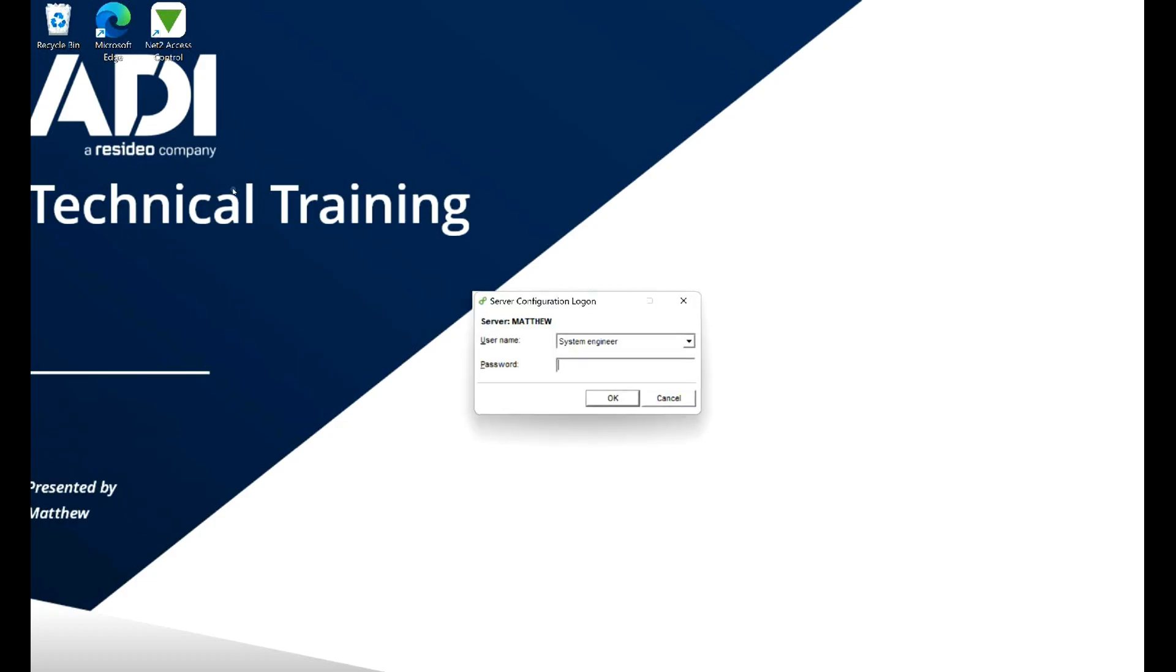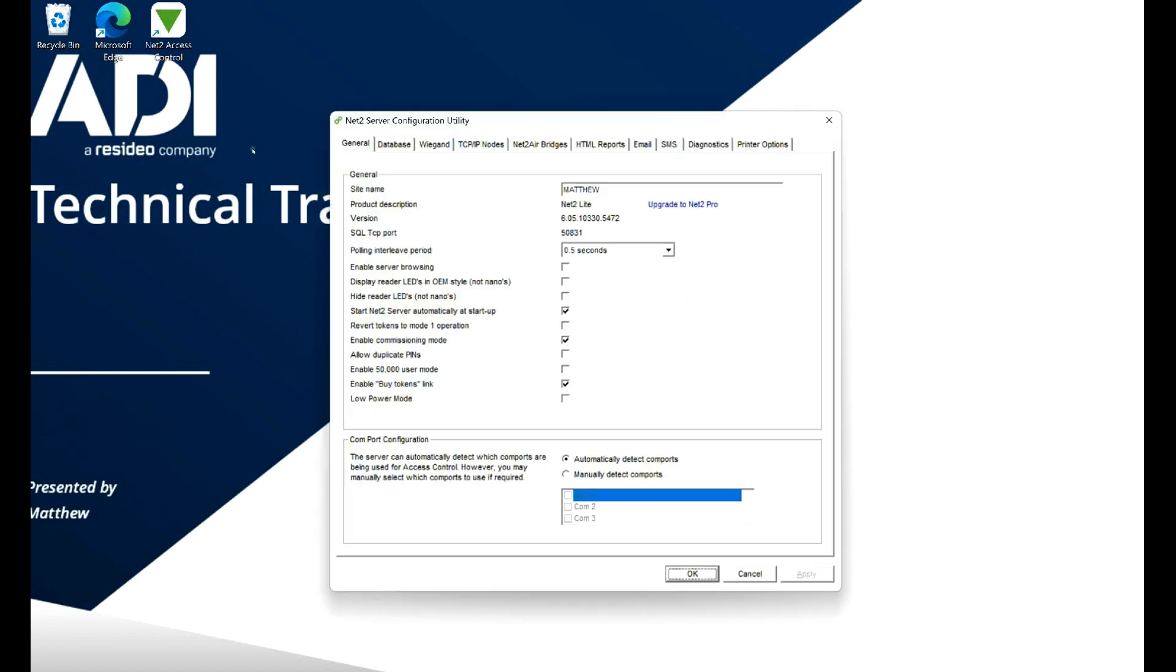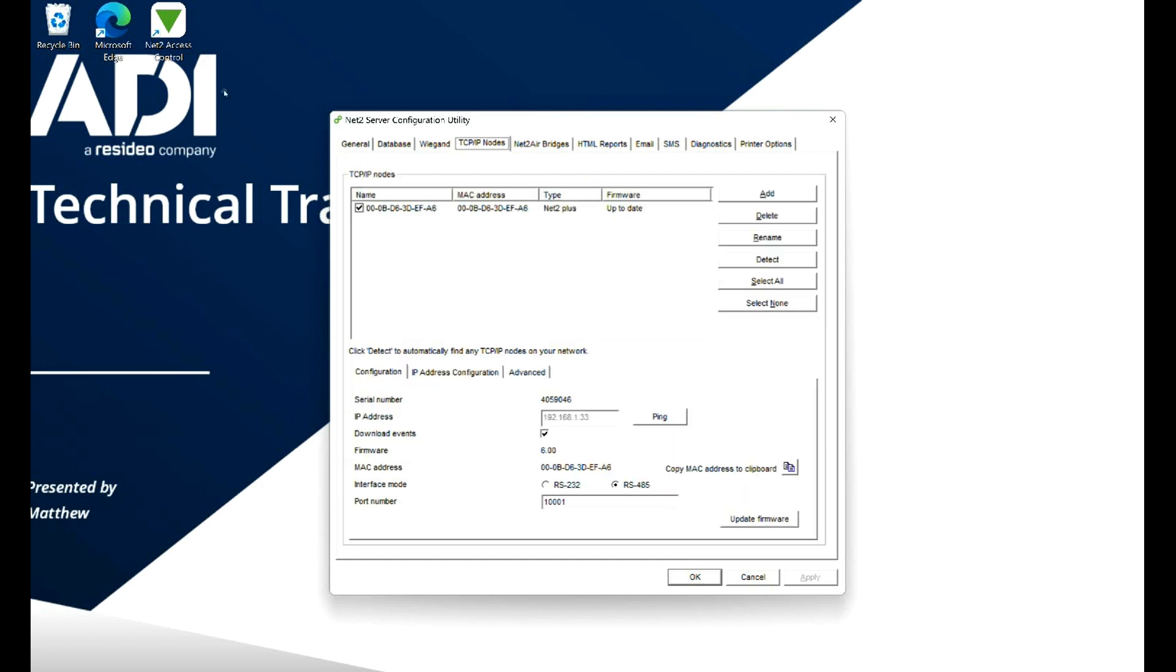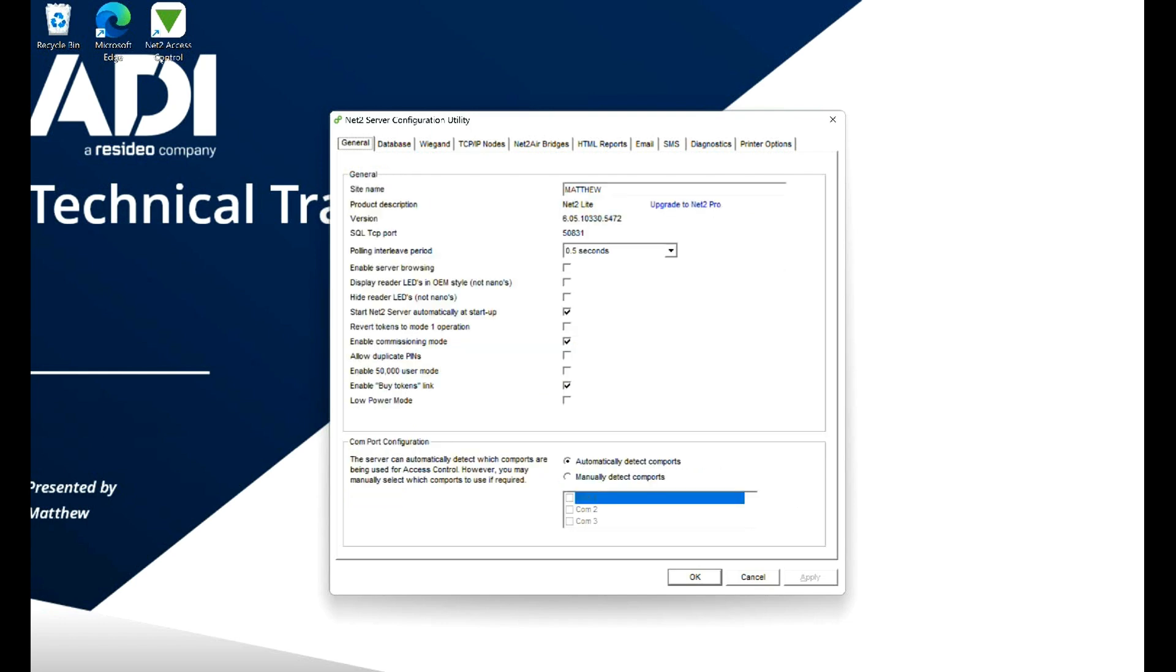First of all, let's go to configuration utility and log in there. This is the Net2 configuration utility. You might find it in the application window. You can see here I've already got a Net2 controller, the TCP/IP node added. We need to go to the general window and in there we can change the LED behavior.